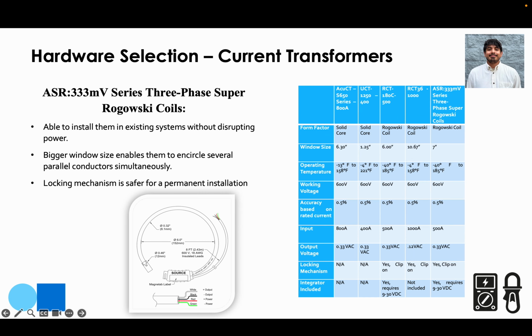For current measurement, we selected the ASR Rogowski coils. One of the biggest benefits of this selection is the ease of installation. They're non-intrusive and don't require power to be shut down to the panel, which is critical for usability in real-world environments. These coils offer large window sizes, allowing us to capture current from multiple conductors simultaneously, and the clip-on locking mechanism adds an extra level of safety for permanent installations.